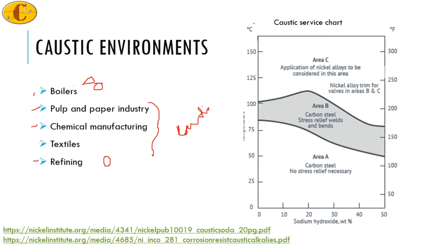There is a caustic service chart that shows the variation of sodium hydroxide concentration with respect to operating temperature, indicating which material should be used at which temperature range. More information about this can be found in documents available from the Nickel Institute.